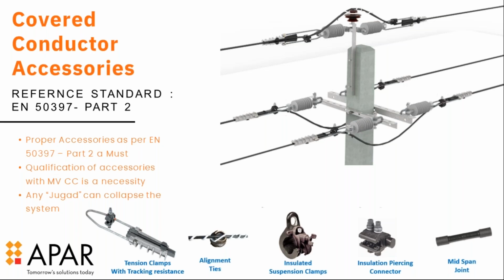We only need to take care of covered conductor specific accessories as per EN standard 50397 part 2, which covers tension clamps. We use tension clamps here too, but the difference is that these have polymeric gripping — you cannot allow any XLPE-covered conductor surface to touch the metallic part, only the polymeric gripping.